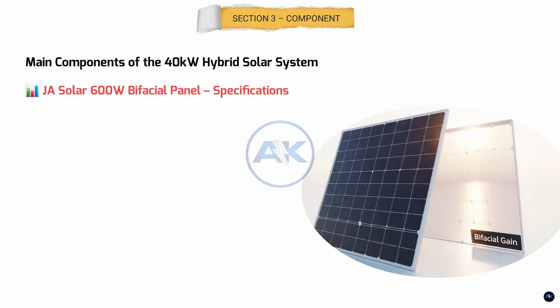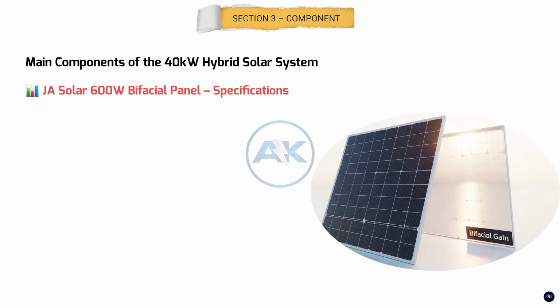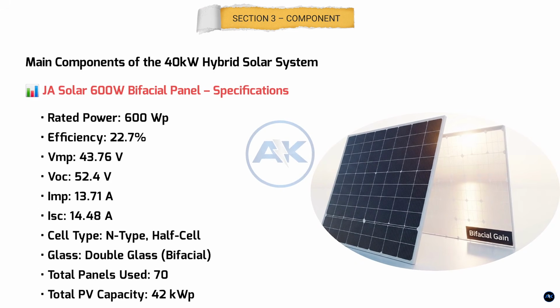Solar generation comes from JA Solar 600-watt N-type bifacial panels. These high-efficiency modules produce power from both the front and rear sides of the panel, increasing total energy yield when installed over reflective surfaces. Each panel has an efficiency of 22.7% with a maximum power voltage of 43.76 volts and a maximum power current of 13.71 amps. In total, 70 panels are installed, providing a combined solar capacity of 42 kilowatts.